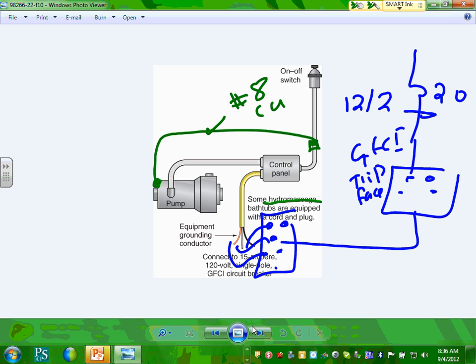I can't emphasize enough, as we move forward, when we have machines, guys, you're going to understand you need an overcurrent protection device, a cable, right? You need some type of protection, whether it's GFCI or not. And then you need a controller that either you provide or the manufacturer will provide. Mechanical equipment, guys, as we move forward, air handling units, chillers, rooftop units, we don't even mess with the controller. It's all provided by the manufacturers. We have no idea if they want a speed control on it, or what type of control, so we end up only providing for mechanical equipment an overcurrent protection device, a feeder, and a disconnect. This will be your disconnect here. Typically, we provide a disconnect, but a lot of manufacturers now provide their own disconnect right next to the equipment.